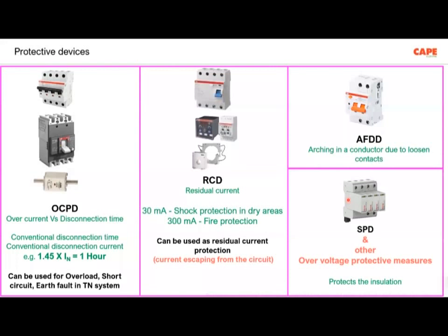Then the next protective device required in your network is the SPD, surge protective device, and other overvoltage protective measures. These protective measures actually protect your insulation. Are we using SPDs in every electrical installation? This is quite rare, I would say. Only in a few places are SPDs used. But the next point, other overvoltage protective measures, is very, very important.